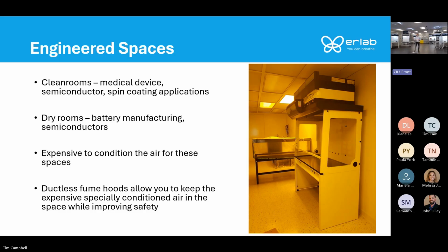So that's where you've got to think, oh, I can improve the safety in the clean room with a ductless fume hood. The other large application we're finding is dry rooms for battery manufacturing. Dry rooms typically have 0% humidity, 5% humidity. Same concept as the clean room. You have all this dry conditioned air going into the space. So if you need to use chemicals, you're probably doing it on the open bench because you're not going to put a ducted fume hood in there.